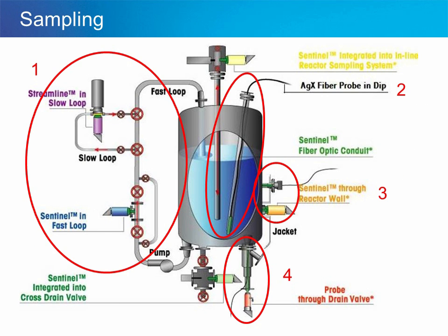Now let's talk about how we actually sample a vessel, or perhaps a stream or pipe, in a continuous process. There are many ways to do this, but I have circled 4 that are by far the most common in our experience. Number 1 shows sampling in a stream or loop. Number 2 shows sampling by putting a silver halide fiber probe into a dip pipe and inserting it through a nozzle at the top of the vessel. Number 3 shows probes inserted directly through the vessel wall, which is usually only practical if the vessel was designed with these inserts in mind. Number 4 shows a probe going through a drain valve, which has turned out to be a rather convenient way to sample large tanks.